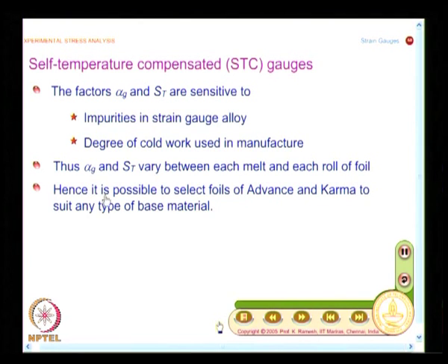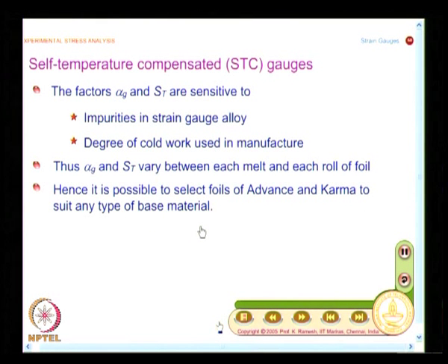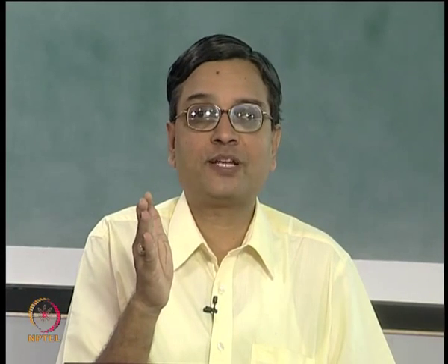In essence, it is possible to select foils of ADVANCE and KARMA to suit any type of base material. Isoelastic is excluded — it is hypersensitive to temperature change, so you do not talk of self-temperature compensated gauges made of isoelastic alloy. We talk only of ADVANCE or KARMA alloy. There is a subtle difference: KARMA alloy covers a larger temperature change range, whereas ADVANCE alloy has a slightly lower temperature limit.